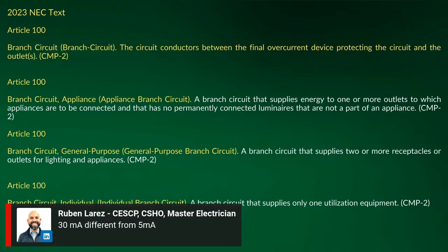If I go to an appliance branch circuit, it says - and Ruben makes a good point that a lot of people do think the 30 milliamp is Class A, and that is a common misconception. It is not. It's just a common misconception that people think you could throw a 30 milliamp device on it and comply with 210.8, the language of 210.8.